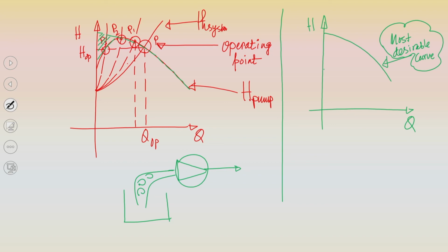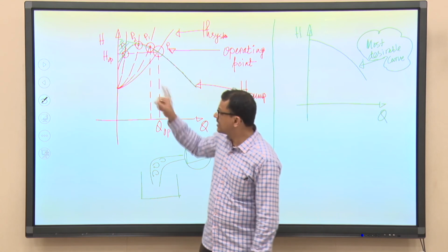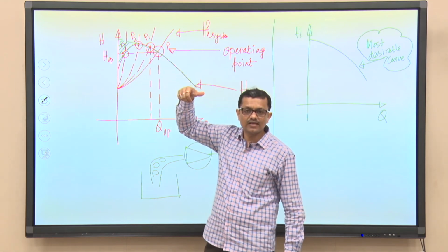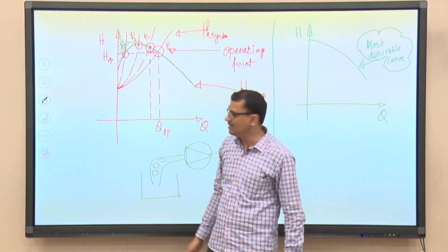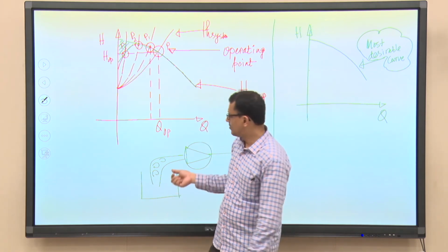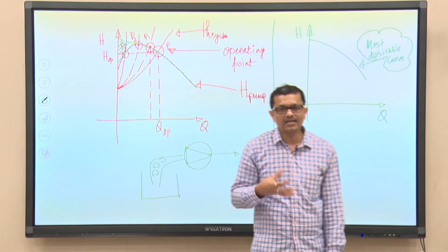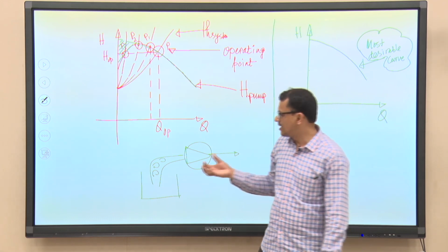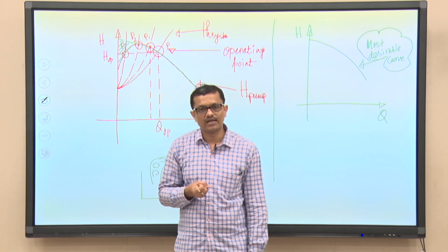These recirculation losses not only change the curve from its continuously drooping characteristic to this type, with an initially increasing trend and then finally decreasing, but also once vortices or eddies are formed at the pump suction site, for their survival these eddies will try to extract energy from the mean flow, right.